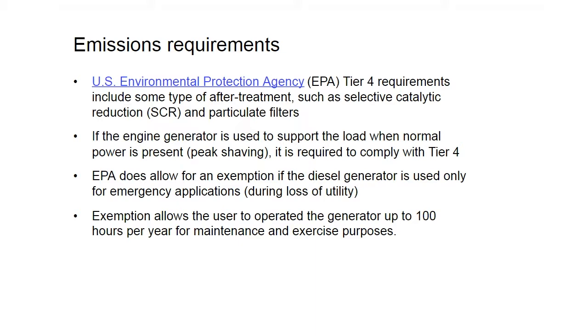Another thing we run into is the emission requirements for mission critical, especially in data centers, where the EPA Tier 4 requirements may include some type of after treatment, such as selective catalytic reduction (SCRs) and particulate filters. Basically, if the engines run any time during normal operation when utility is available, they're going to require a Tier 4. So if you're doing peak shaving or so forth, they're going to require that extra requirements.